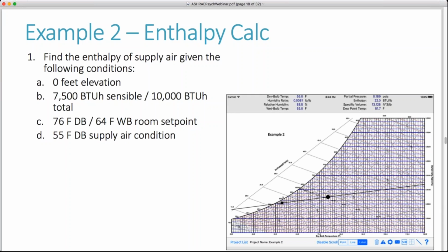Okay. The second example is also fairly simple. It's an enthalpy calculation. So we want to find the enthalpy of supply air given the following conditions. These conditions are 0 feet elevation again, 7,500 BTU per hour of sensible, 10,000 BTU per hour of total cooling load, our set point 76 dry bulb, 64 wet bulb, which is our room set point, and then 55 degree supply air condition.